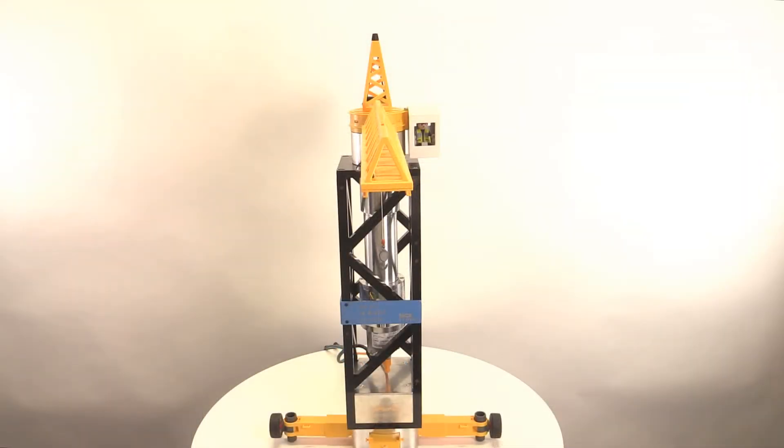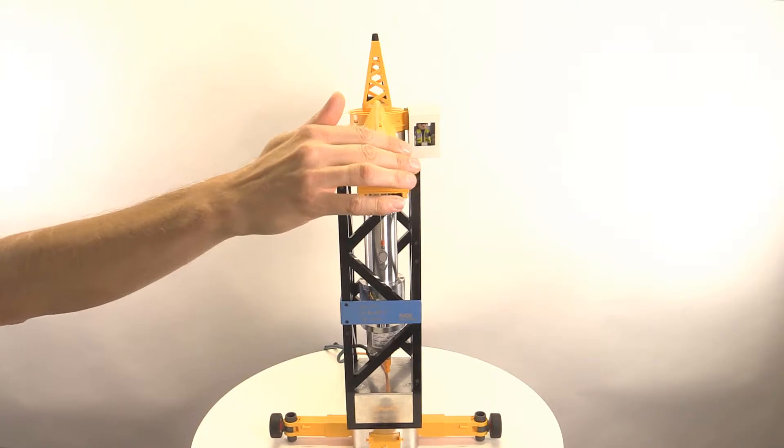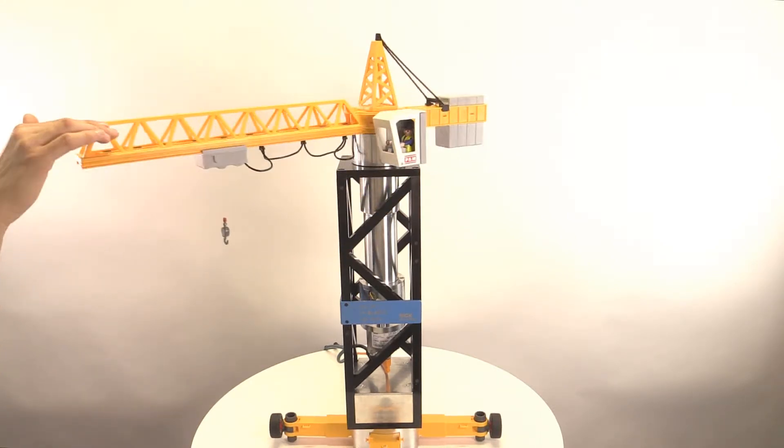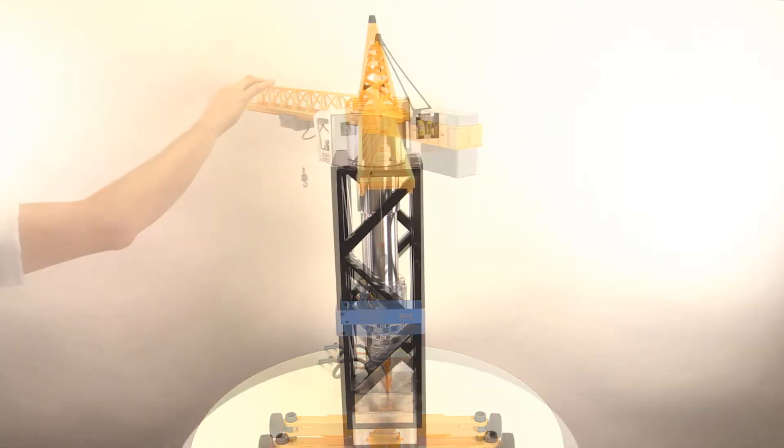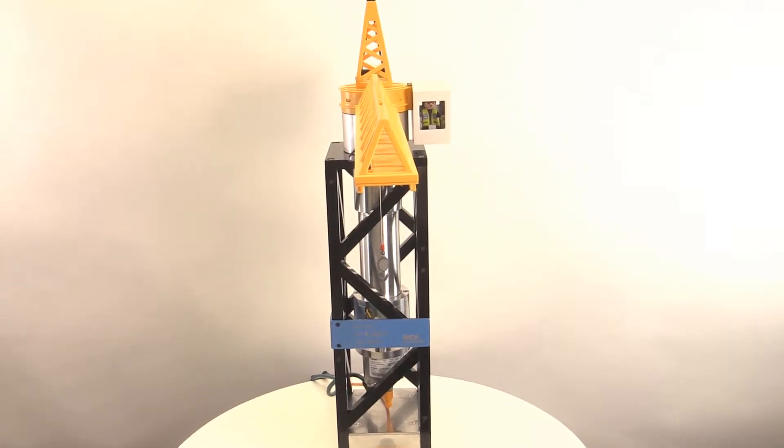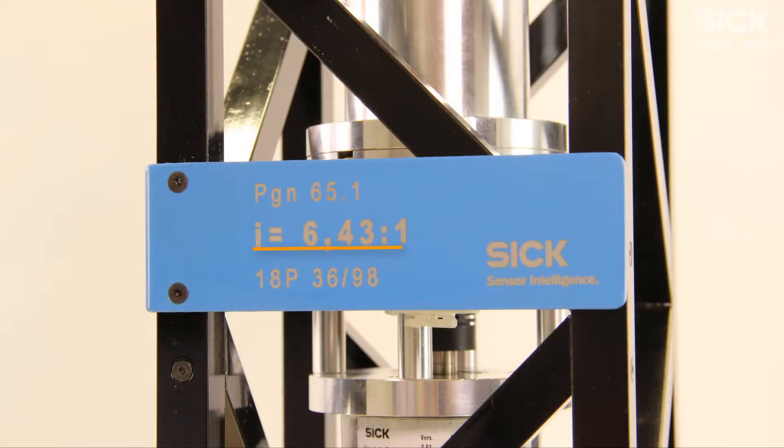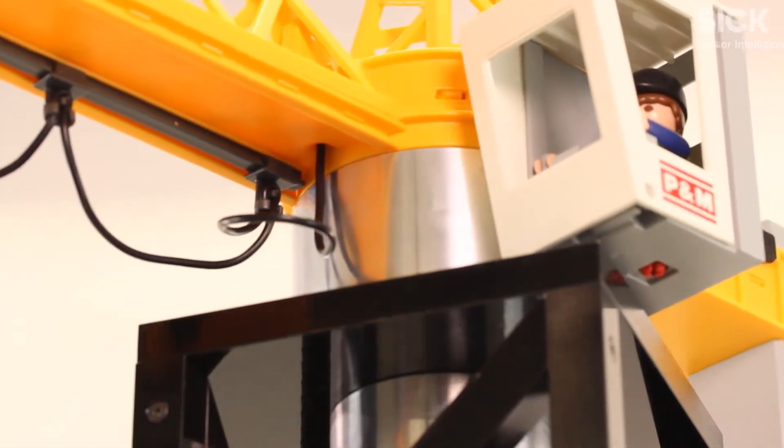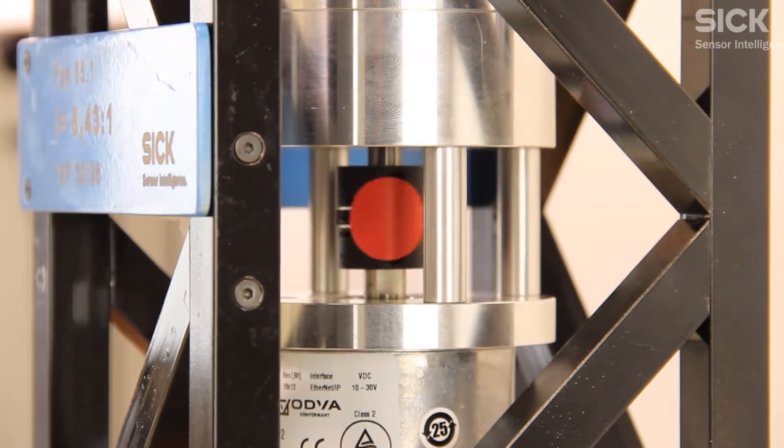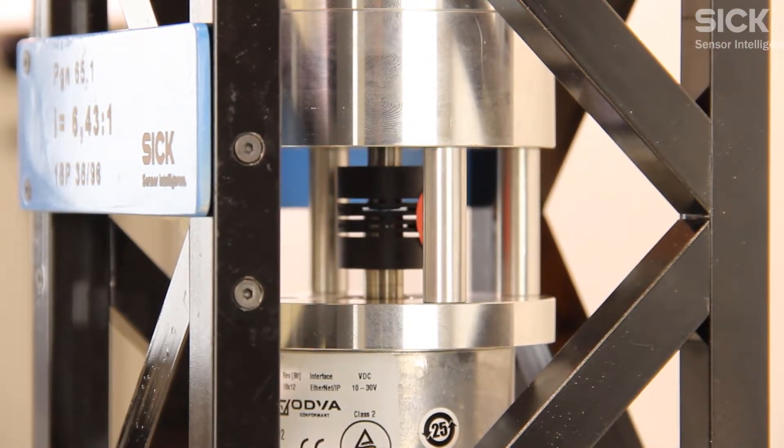As reference, we are using a small demo example of a crane with rotatable boom. The rotation of the crane is transmitted to the encoder via a gear motor with a ratio of 6.43 to 1. This means when the boom is turning one revolution, the encoder shaft turns 6.43 times.